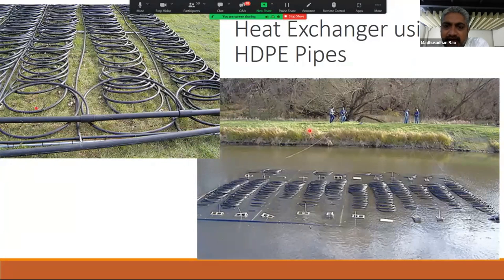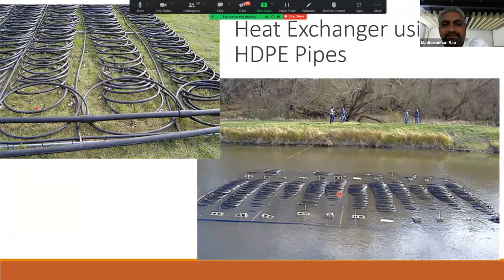So essentially what you're doing is you're getting rid of the cooling tower and evaporation mechanism and using sensible heating of a large body of water. Now, I understand that a large body of water may not be possible everywhere. We'll discuss that later, but wherever it is feasible, okay? There is enough water, we'll come to that. You can put an HDPE-based heat exchanger. Basically, this is the piping network you would put in the ground in a geothermal heat exchanger. All I'm saying is put that in water. You will get better performance, and year on year, better performance, no degradation, no derating.